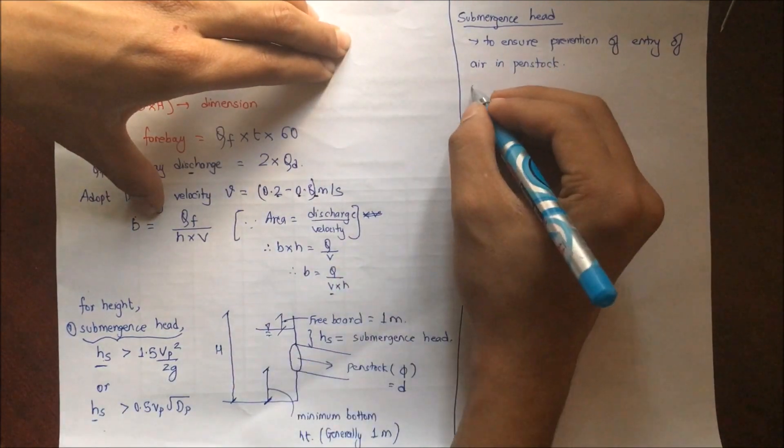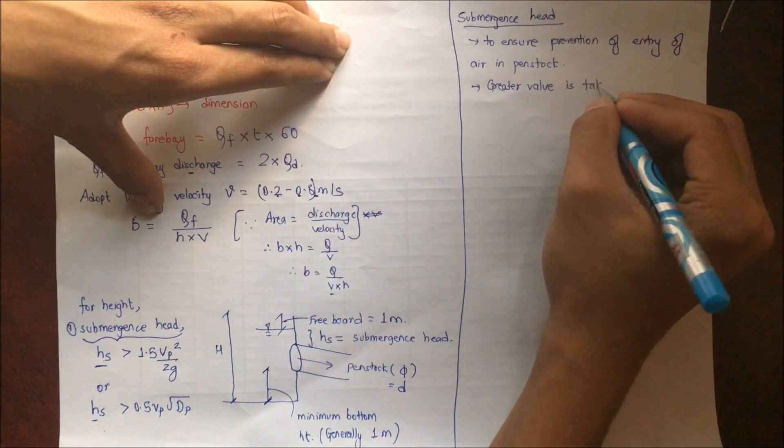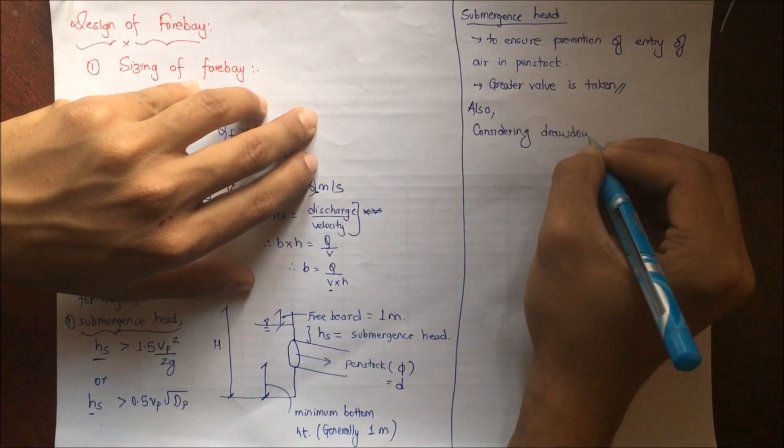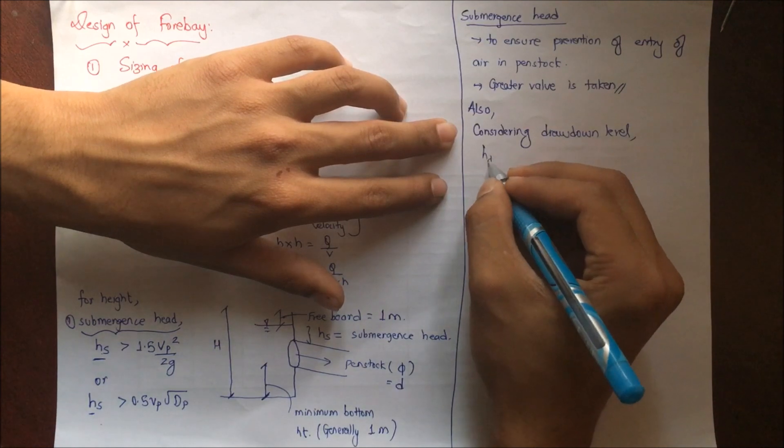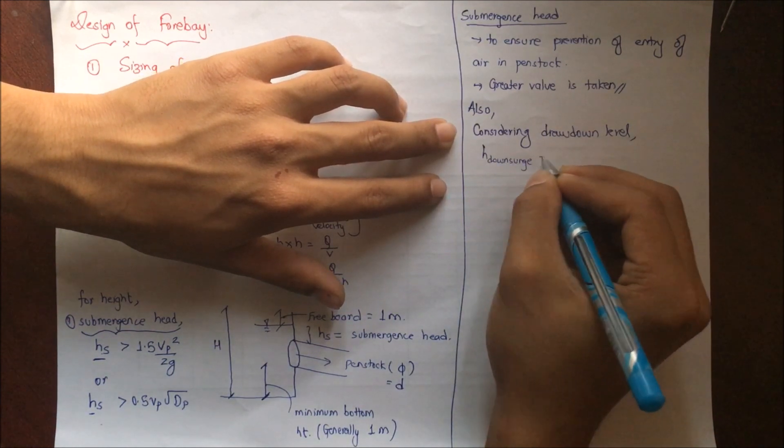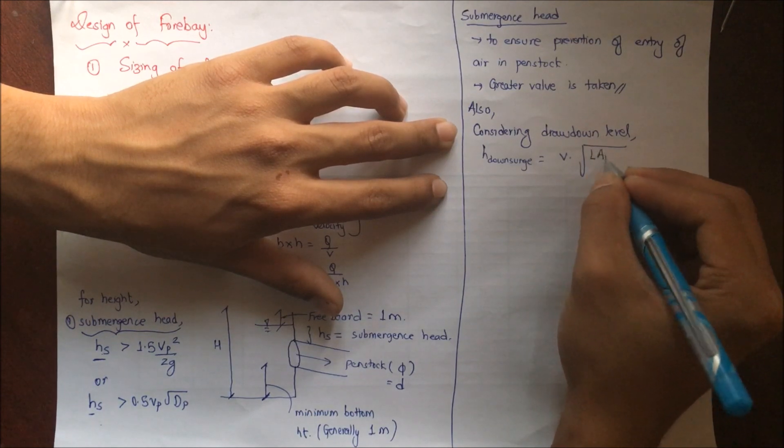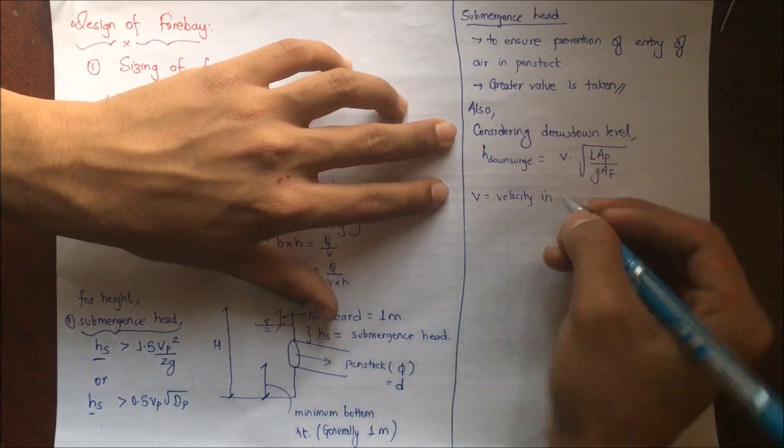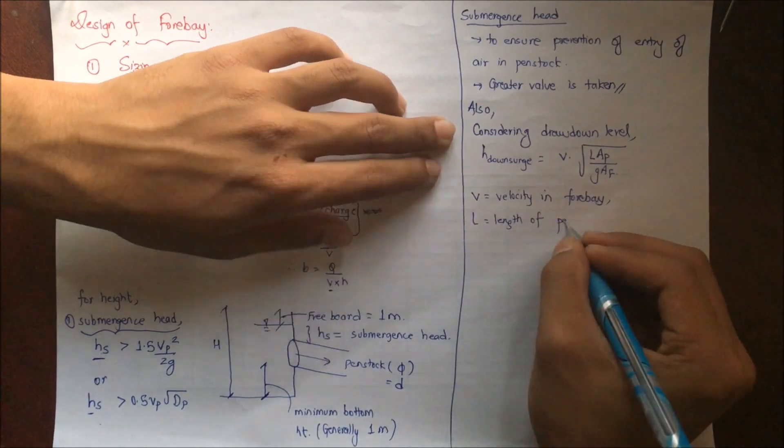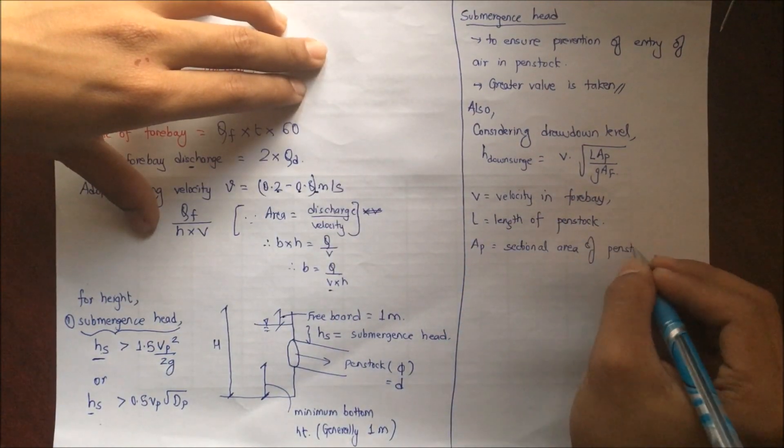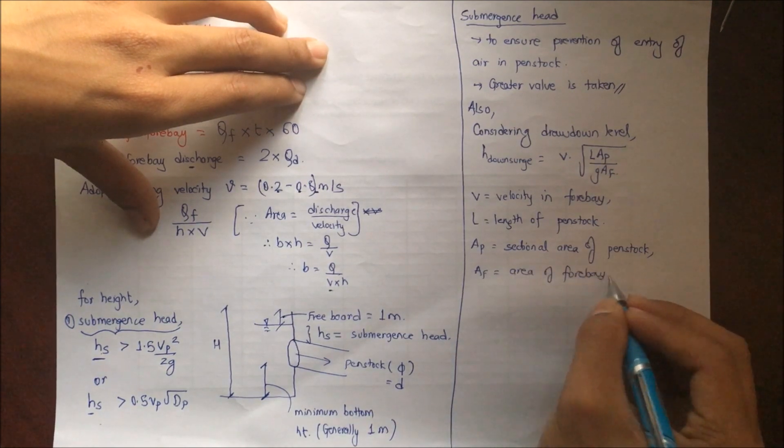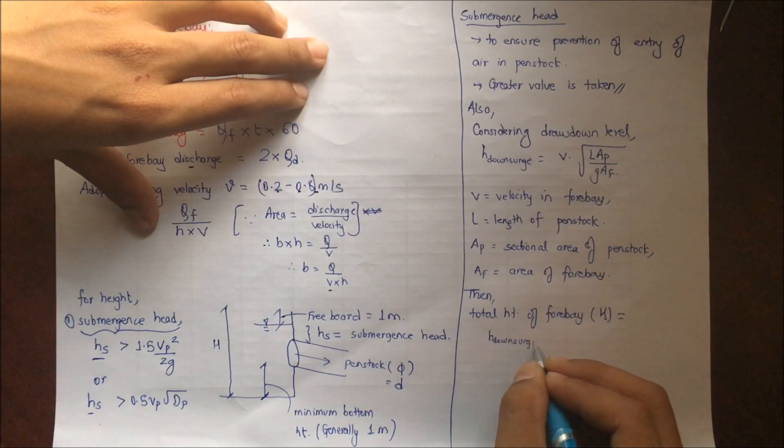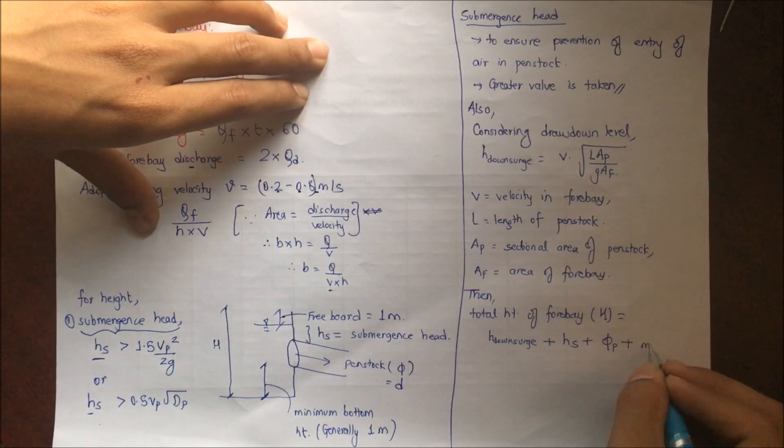Submergence head is provided to ensure prevention of entry of air in penstock. We have derived two values, so greater value between these two is taken. Also we have to consider the drawdown level for the prevention of entry of air in penstock. H downsurge = V × √(Lap/gAf). What are these terms? V is velocity in forbay, L is length of penstock, Ap is sectional area of penstock, Af is area of forbay. Then total height of forbay H will be equal to H downsurge + Hs + diameter of penstock + minimum bottom height + freeboard.